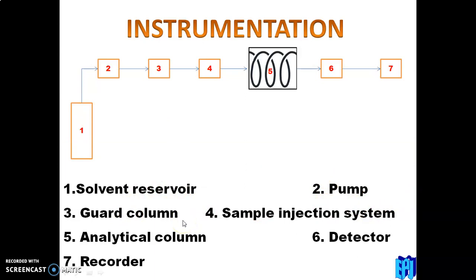The guard column guards the analytical column. The solvent in liquid form may contain some impurities, which could damage the analytical column. If the analytical column breaks, the instrument cannot be used. Therefore, we must filter the solvent before it reaches the analytical column, using the guard column.